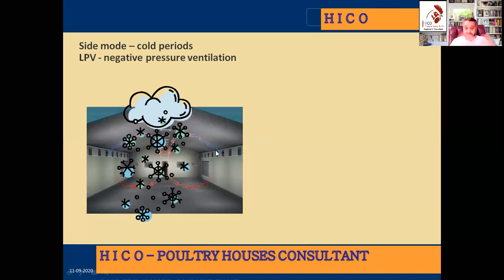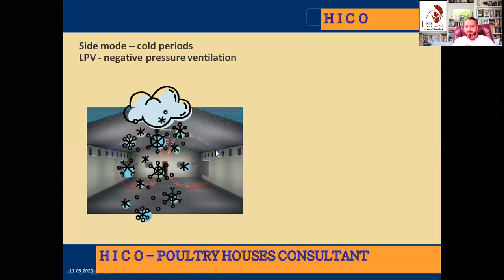You must remember that if your house temperature is more than 3.5 to 4 degrees Celsius above outside, you should stay in the side mode condition, taking air from the inlets. After that threshold you transition to tunnel ventilation. Side mode and minimum ventilation are similar, but with this key difference in how fans operate.